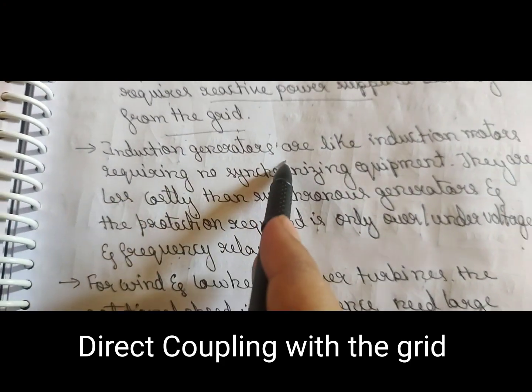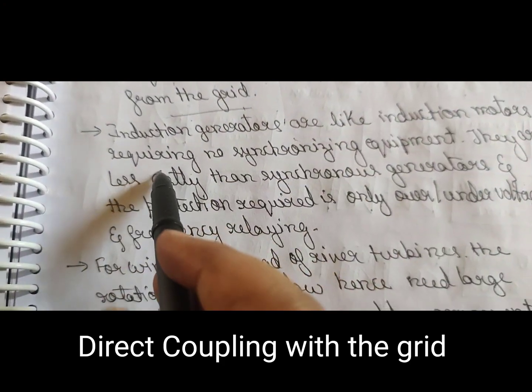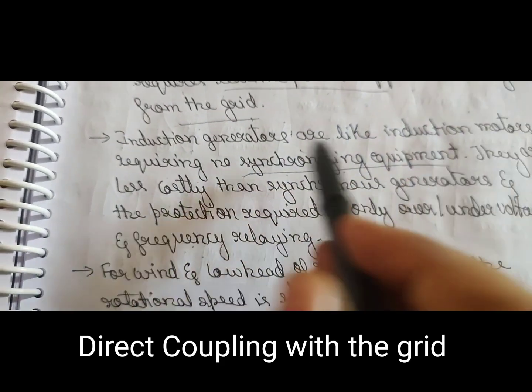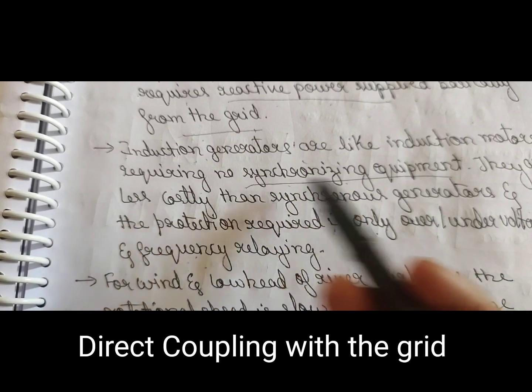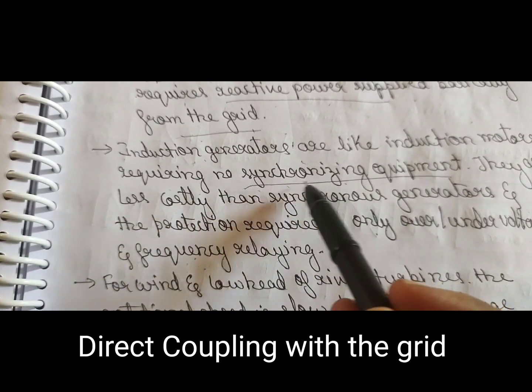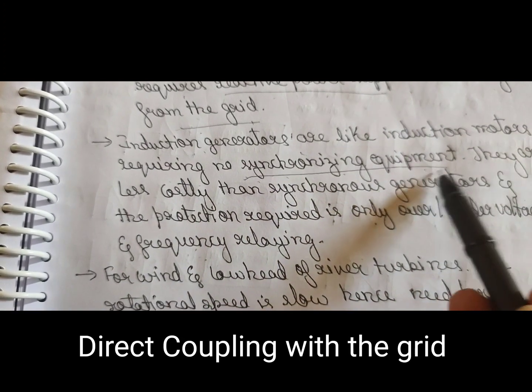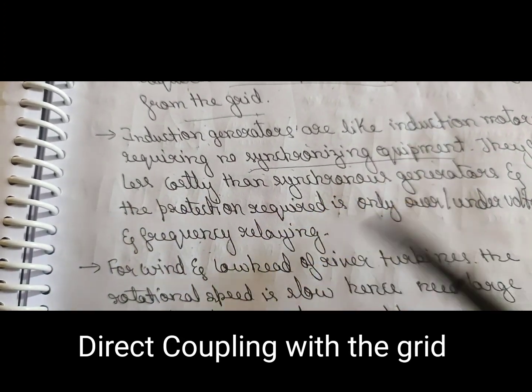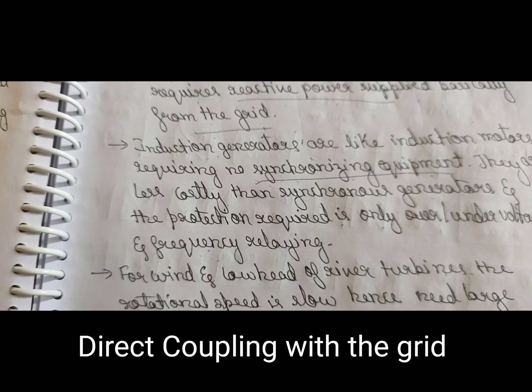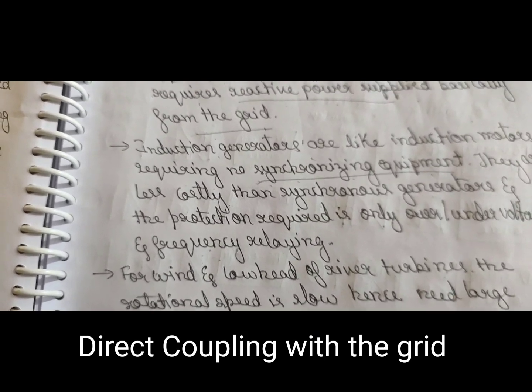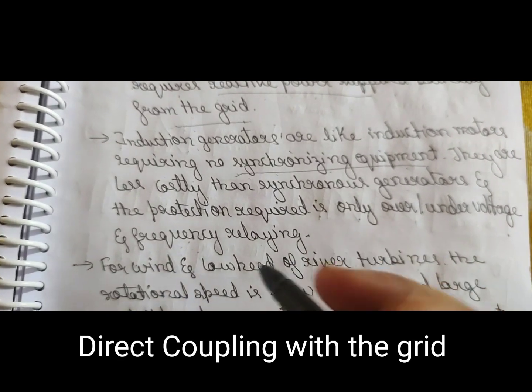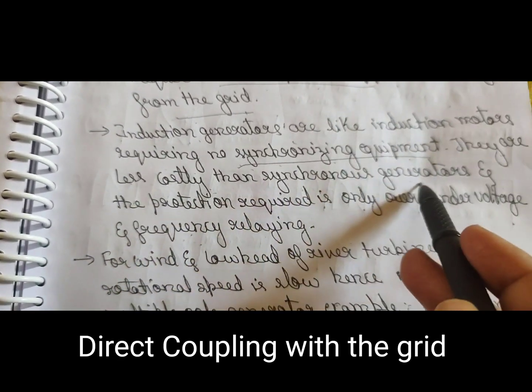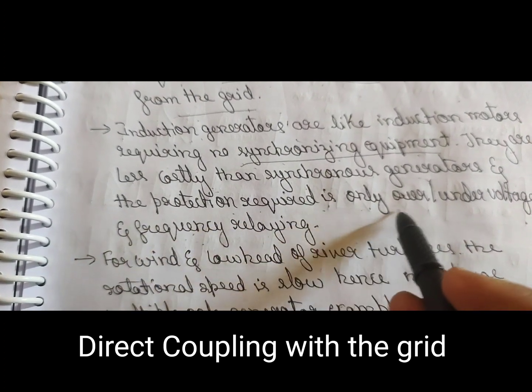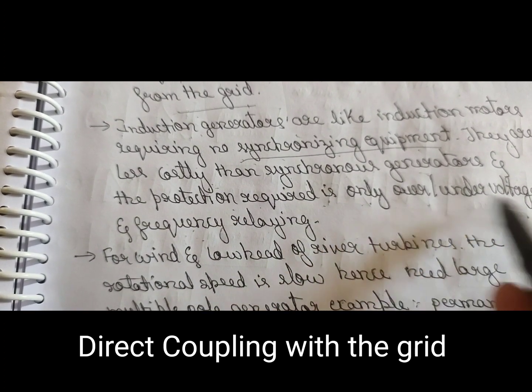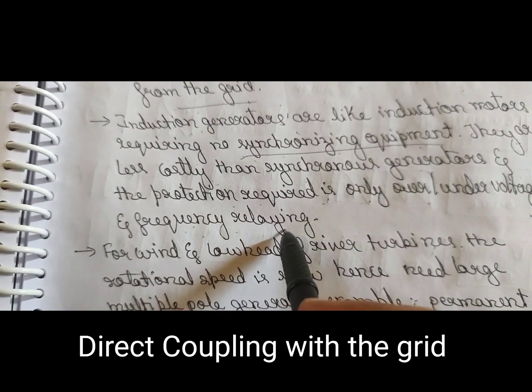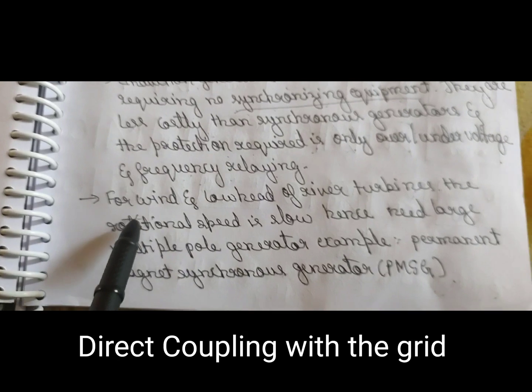Induction generators are like induction motors, and require no synchronizing equipment. They are less costly than synchronous generators. If we compare cost-wise, induction generators are less costly, and the protection required is only over and under voltage and frequency relaying.